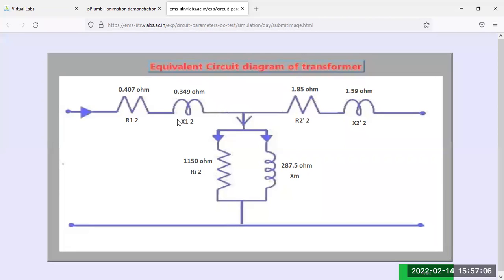Now, how do you calculate R1, X1, R2 dash and X2 dash? Just take the data of the short circuit test, that is, the power consumption during the short circuit test. The power consumption was 37.5, the voltage rating was 11 volt, and the short circuit current rating was 4.5 ampere.